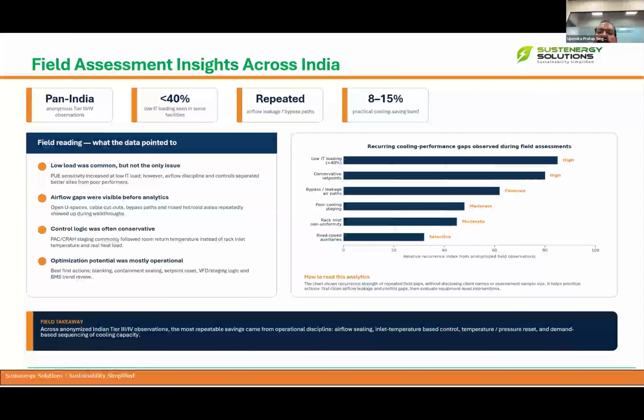Then control logic: sometimes they always keep it conservative. So instead of setting a temperature of 24 or 23, they will always set a temperature of 20 degrees, 19 degrees, like that. Also, sequencing is mostly done manually. Many sites don't have any proper BMS or control logic to operate the PACs. It is based on operator judgment, so they can switch on any unit or switch off any unit. Sometimes they also switch on the standby units, which removes further redundancy. Those things need to be taken care of, and the operators need to be trained properly.